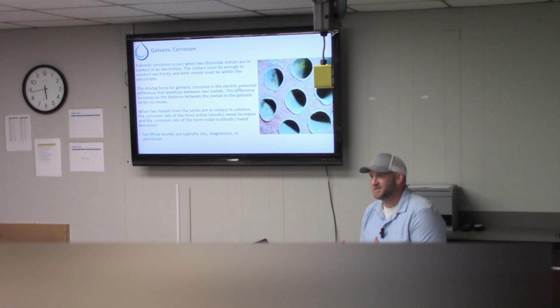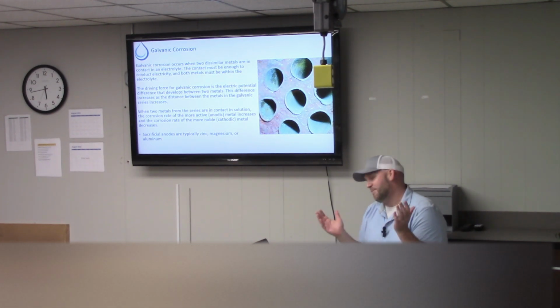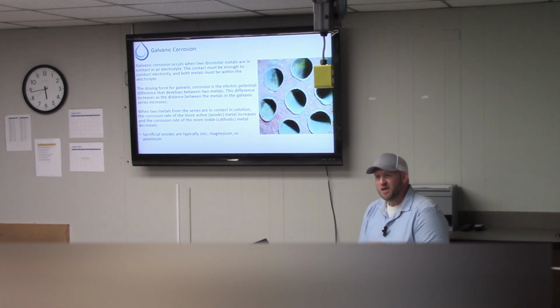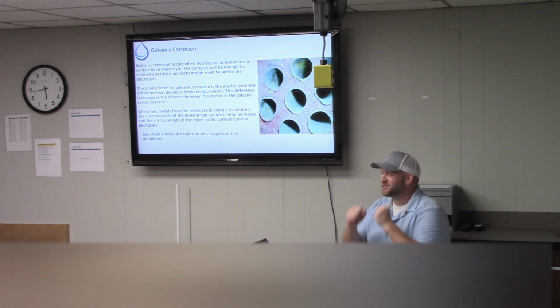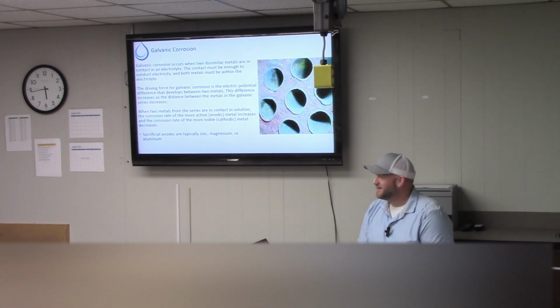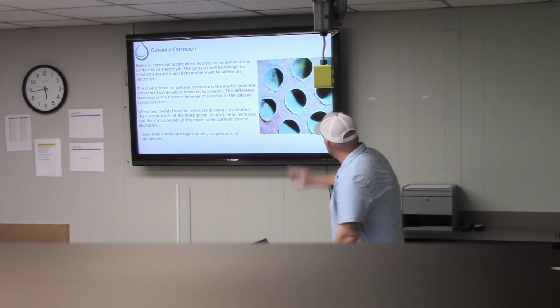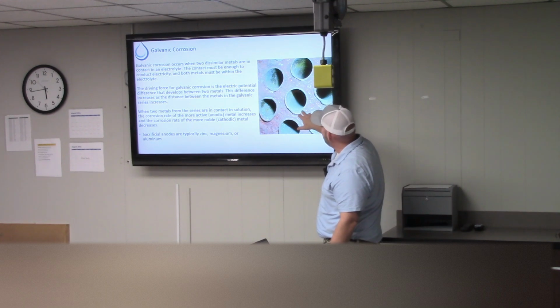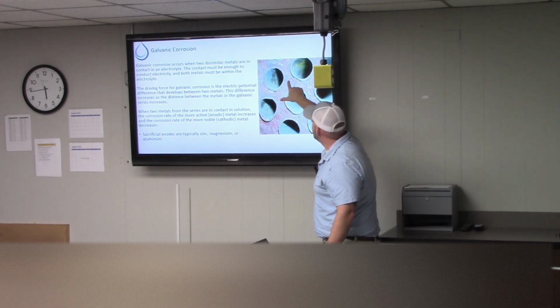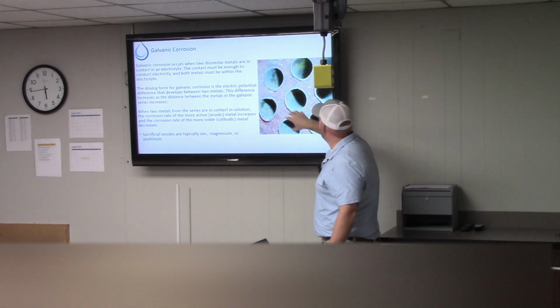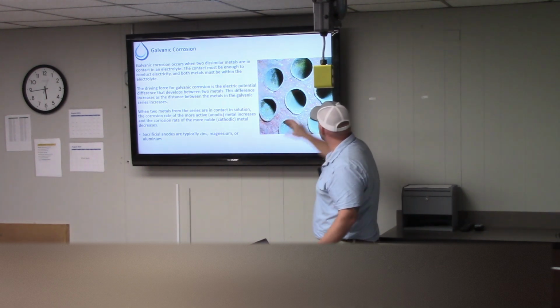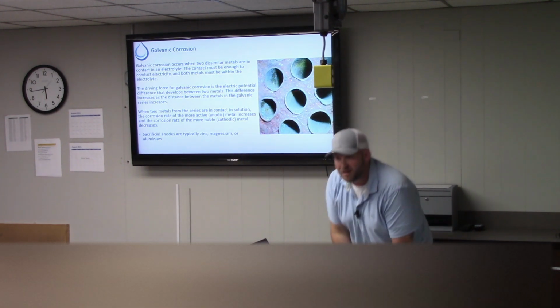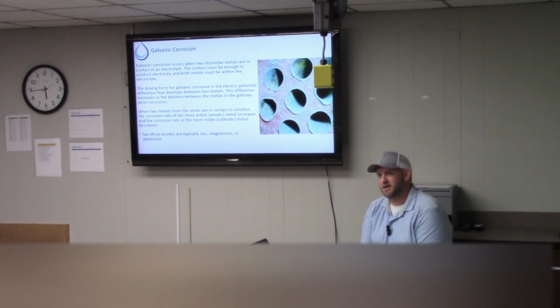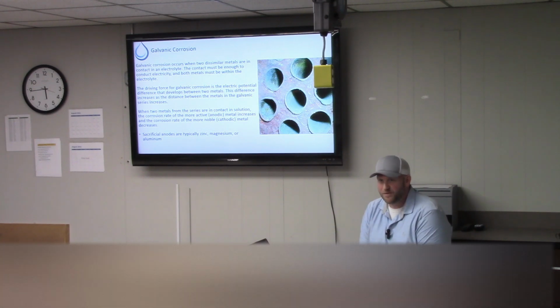Specifically, going above 8 feet per second velocity through a copper pipe or a copper nickel pipe will encourage erosion corrosion. The velocity will start to rip apart the pipe and start depositing little pieces of copper on the steel and start this type of corrosion. You will see the droopy, pouty lips of the pipes. That's the copper going away. Everything else around it are the little drills where this galvanic corrosion is occurring and is just drilling through it at a rate that is oftentimes terribly accelerated. 5x, 6x, could cause a piece of equipment to need significant change out of components in as soon as years.